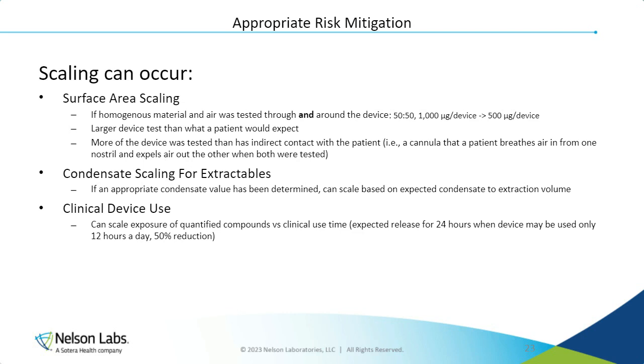If a larger device, maybe a family representative device, was tested, but a smaller device may be used by a patient, say 70% of that, we could apply a scaling factor lowering that clinical exposure. Let's also say certain aspects of the device were tested. However, they may not ever come into contact with the patient.